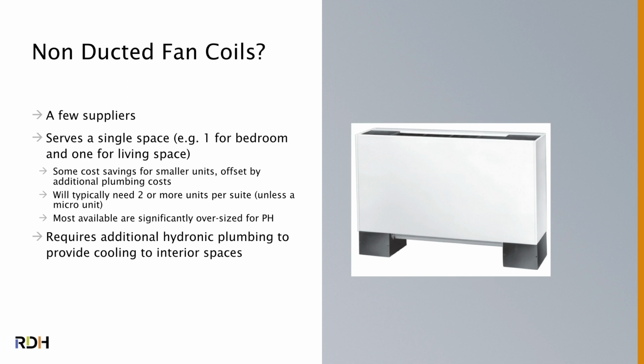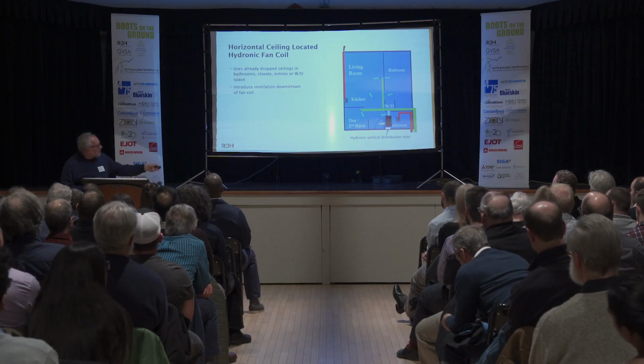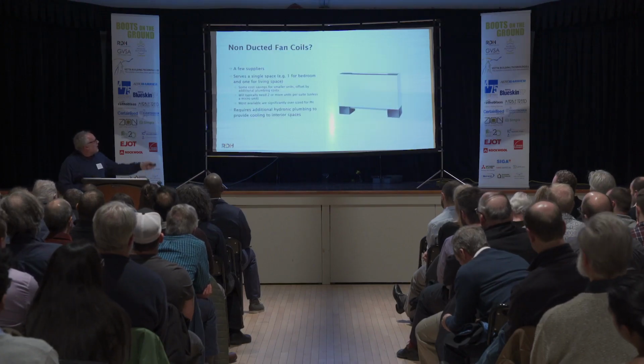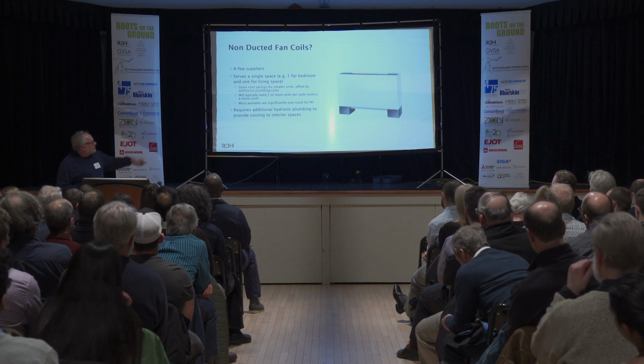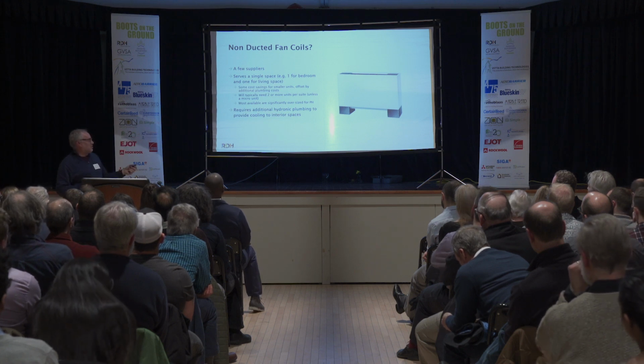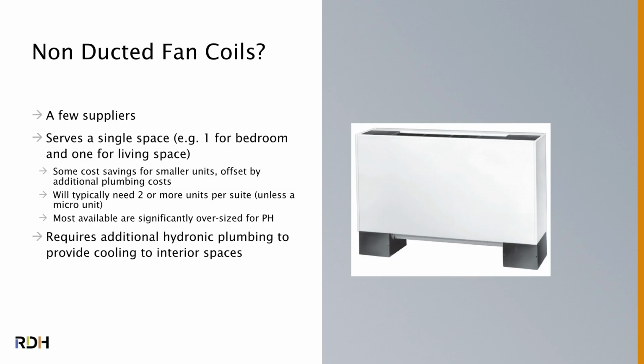There are non-ducted fan coils. They don't look that much different from the old window shakers in your hotel room. They run off hot and cold water. So again, sorry, backing up, there's a hot water distribution riser there, hot and cold water. But most of them are still pretty large. They tend to be still 2 and 3 times bigger than we need.